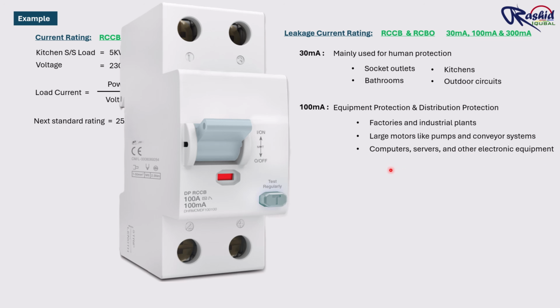So when many devices are connected together, these small leakages can add up. If we use a 30 mA RCCB or RCBO for the complete system, it may trip frequently even when there is no dangerous fault. So to avoid this, a 100 mA RCCB is often used. This is the reason why we use a 100 mA RCCB.